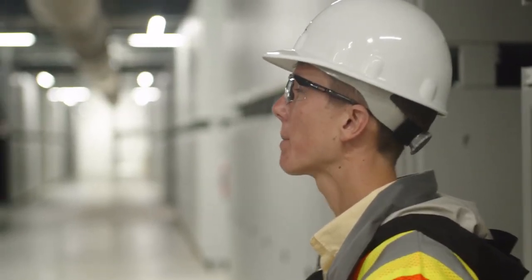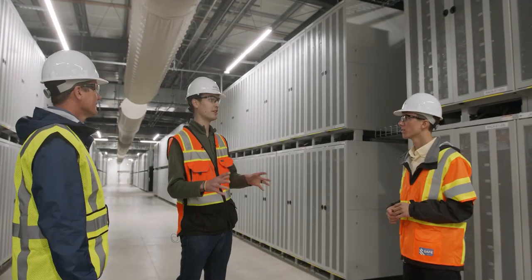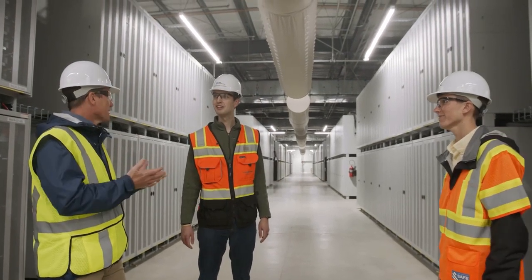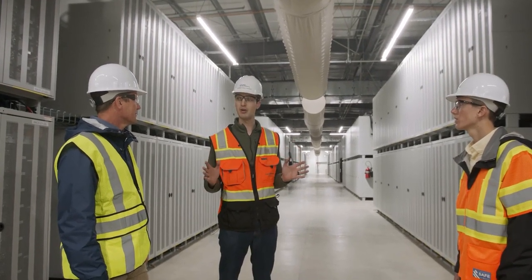How many megawatts does this storage facility hold? This is a 100 megawatt facility — that's power — and the energy is really what the batteries define. It is a 400 megawatt hour nameplate facility. So 400 megawatts — what does that mean? Can you put that in perspective? 100 megawatts is the power, and 400 megawatt hours basically means that they can get 100 megawatts of power for 4 continuous hours on a discharge.